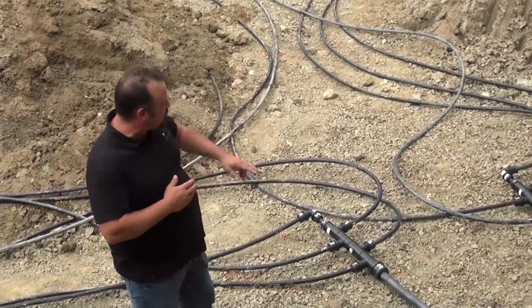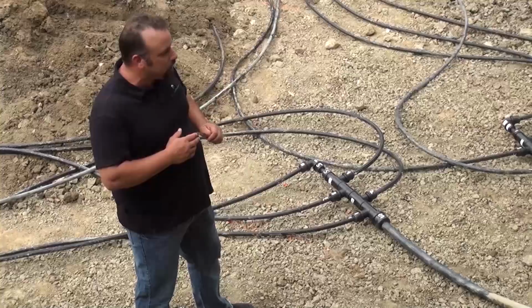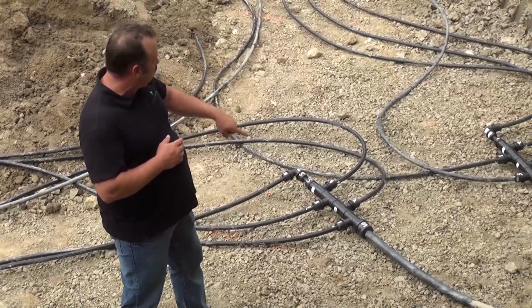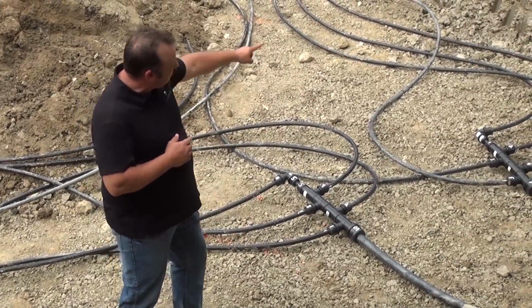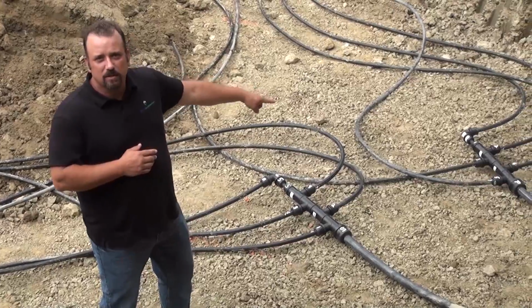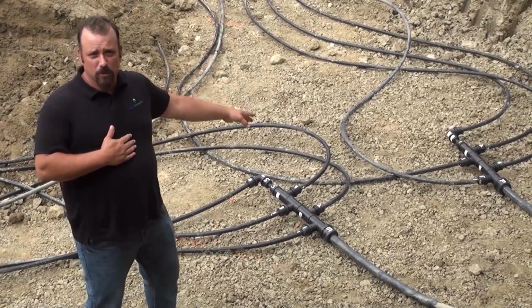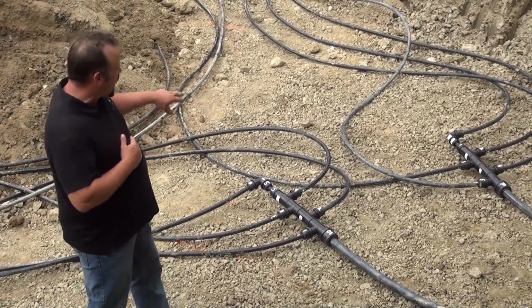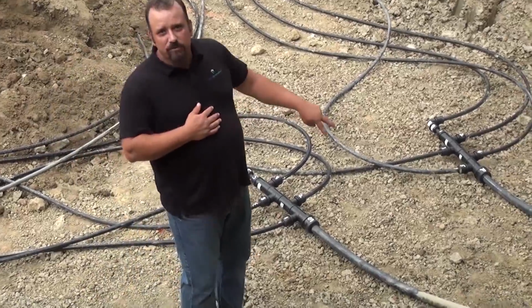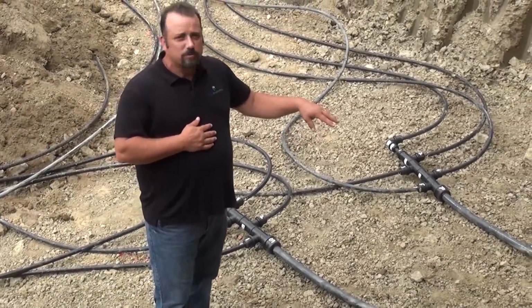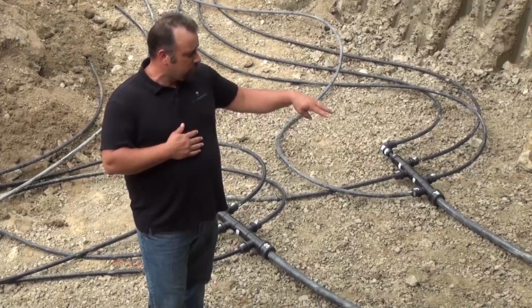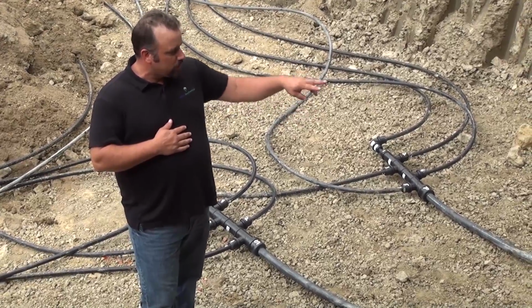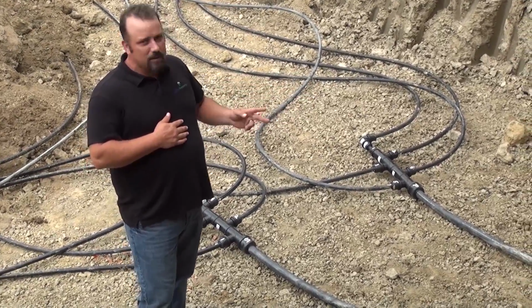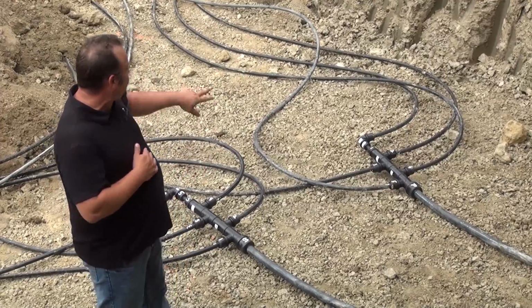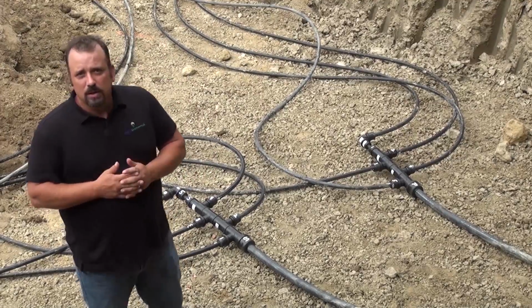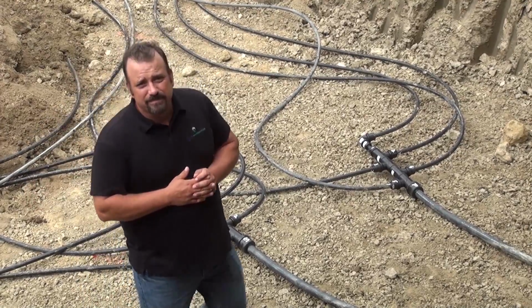So these lines, again, come into this manifold. Every loop that supplies out, that goes out first, comes back last on the return header. That's why I said two-pipe reverse return in the very beginning. Then these lines are 1.5 inches, which is enough water and fluid volume, with the ethyl alcohol volume, 1.5 inches is what we needed on this particular application to carry all the fluid that runs through this loop for the horizontal system.